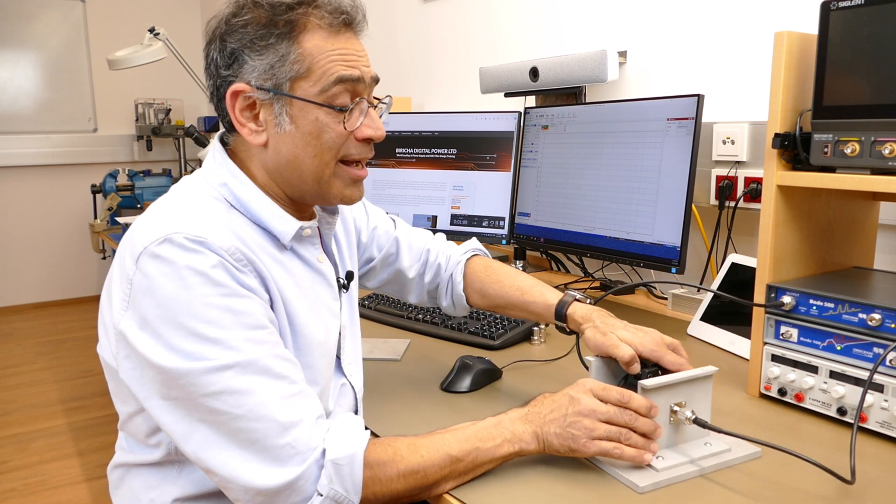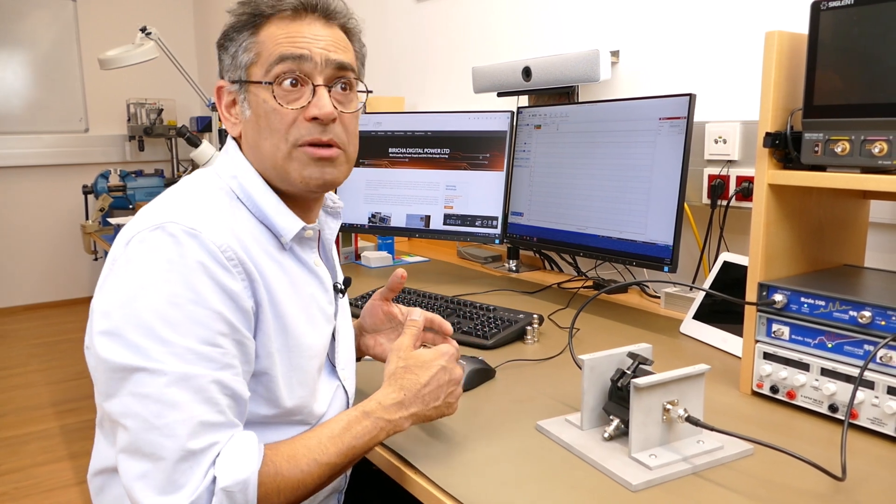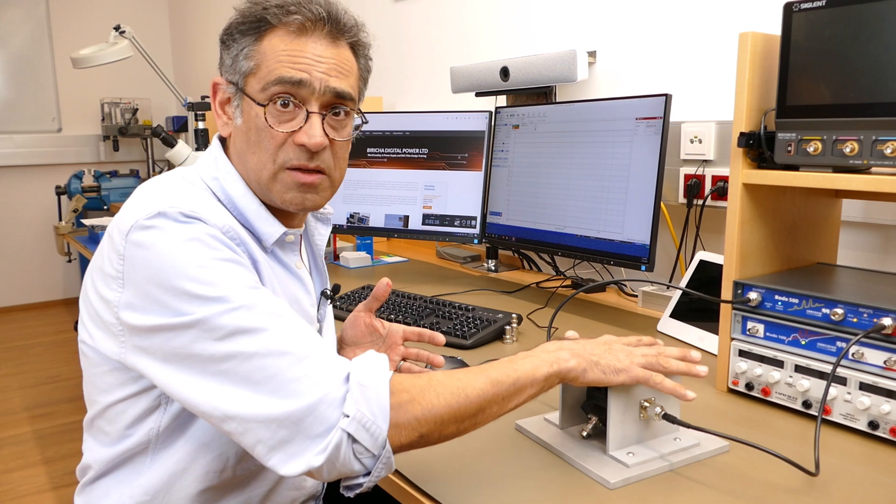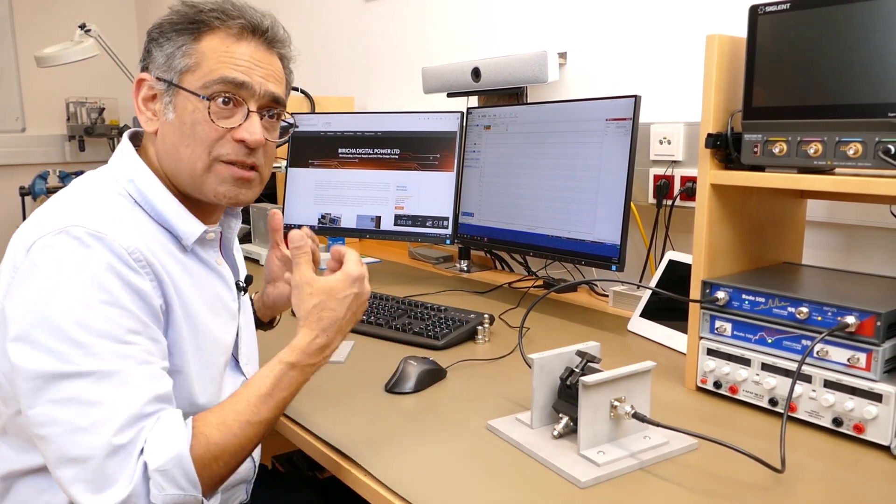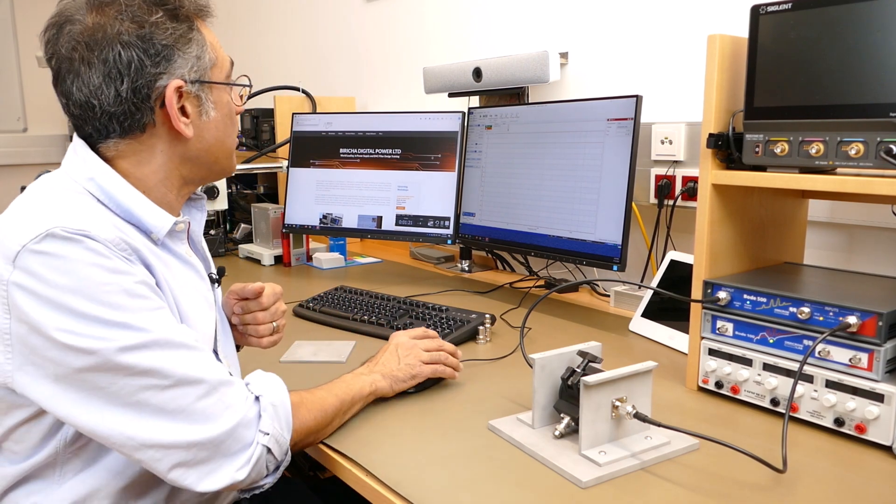We are talking at very high frequencies - we're going from 100 kilohertz to let's say 350 megahertz in this particular case - and there's bound to be some anomalies. So the first thing that we have to do is normalize our measurement. At the moment if I make a measurement on my Bode 500, you will see that as the frequency goes higher here, the measurement is not quite correct and we need to normalize it.